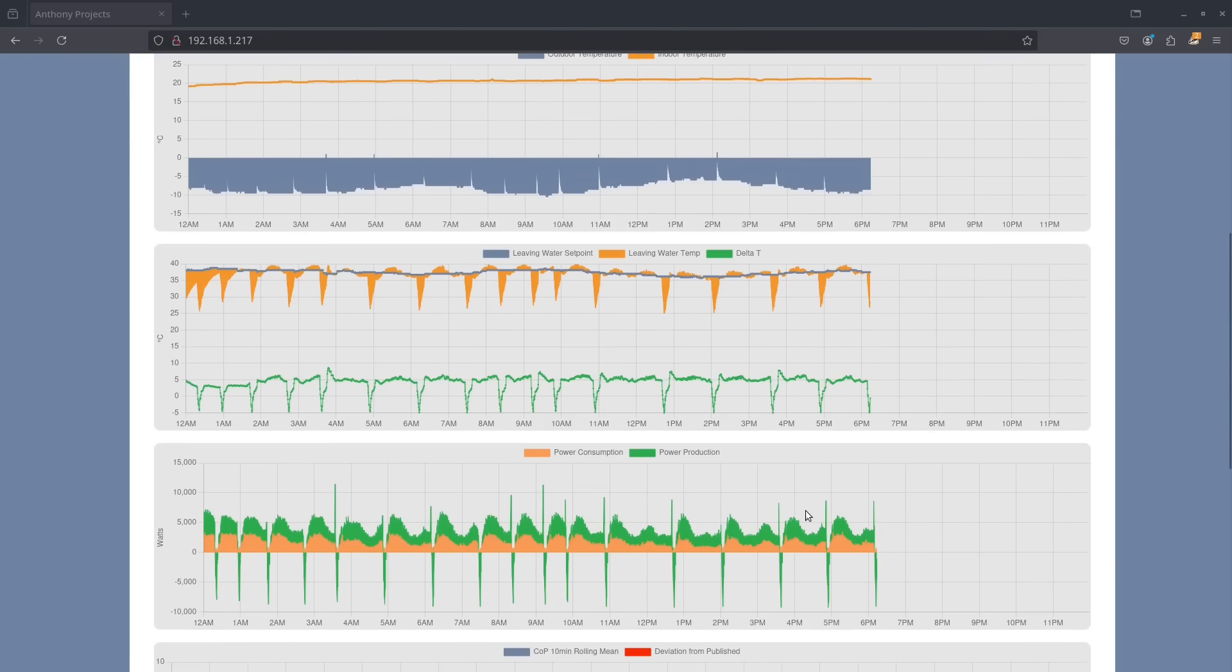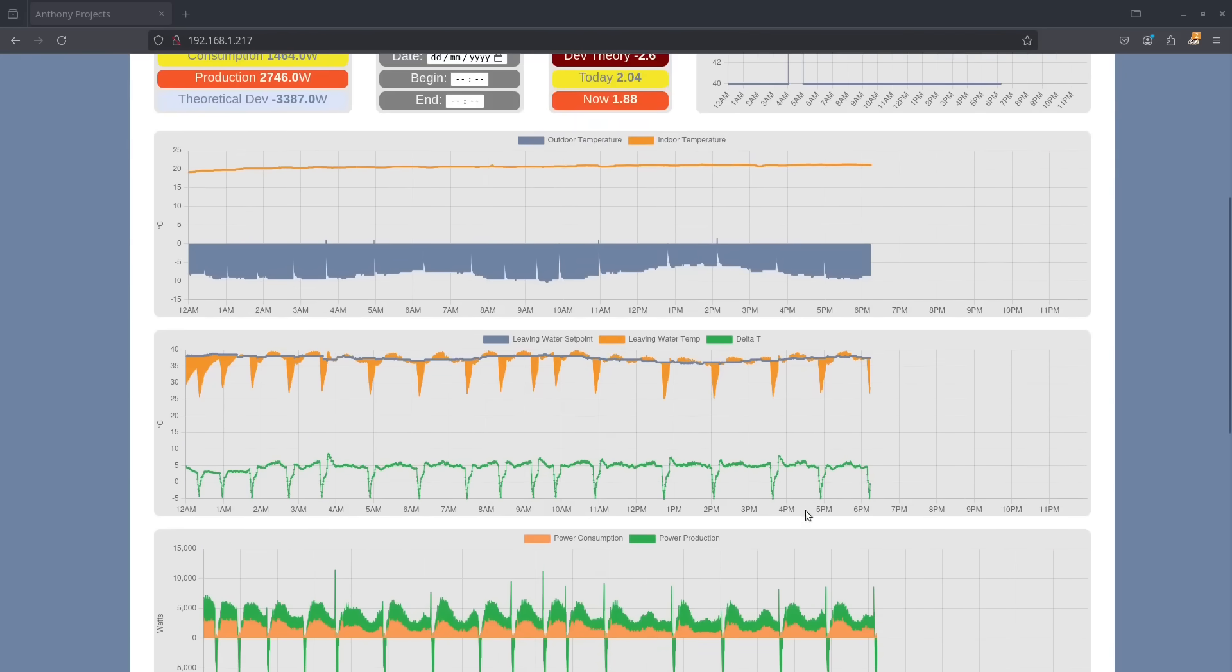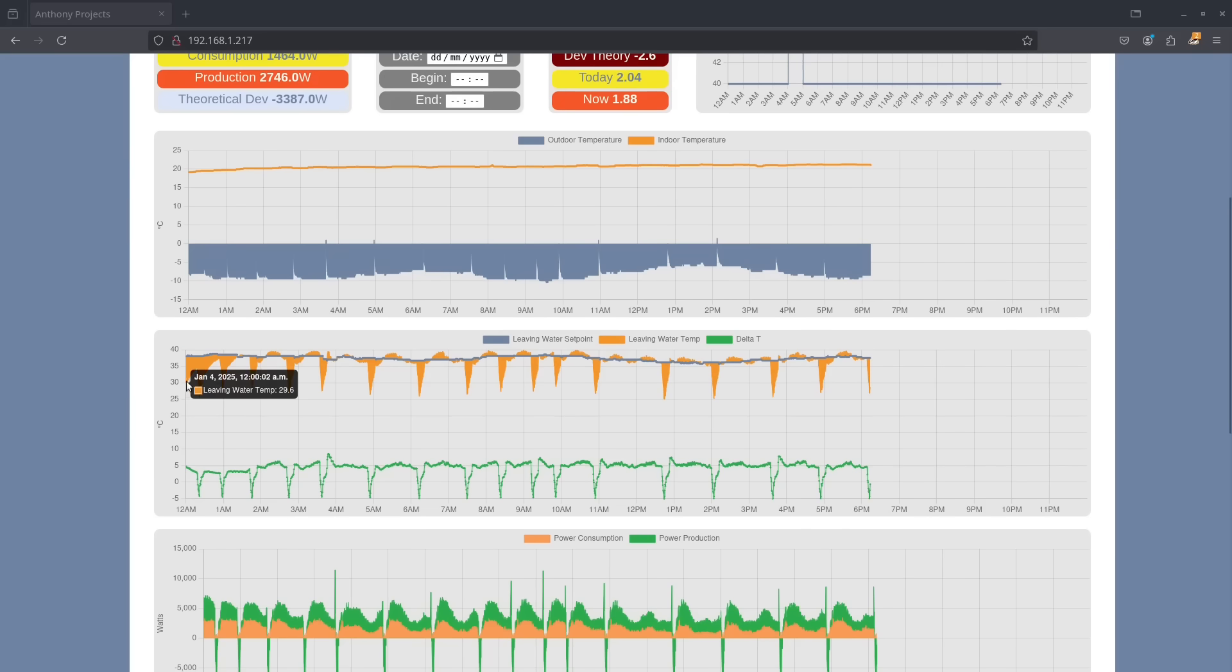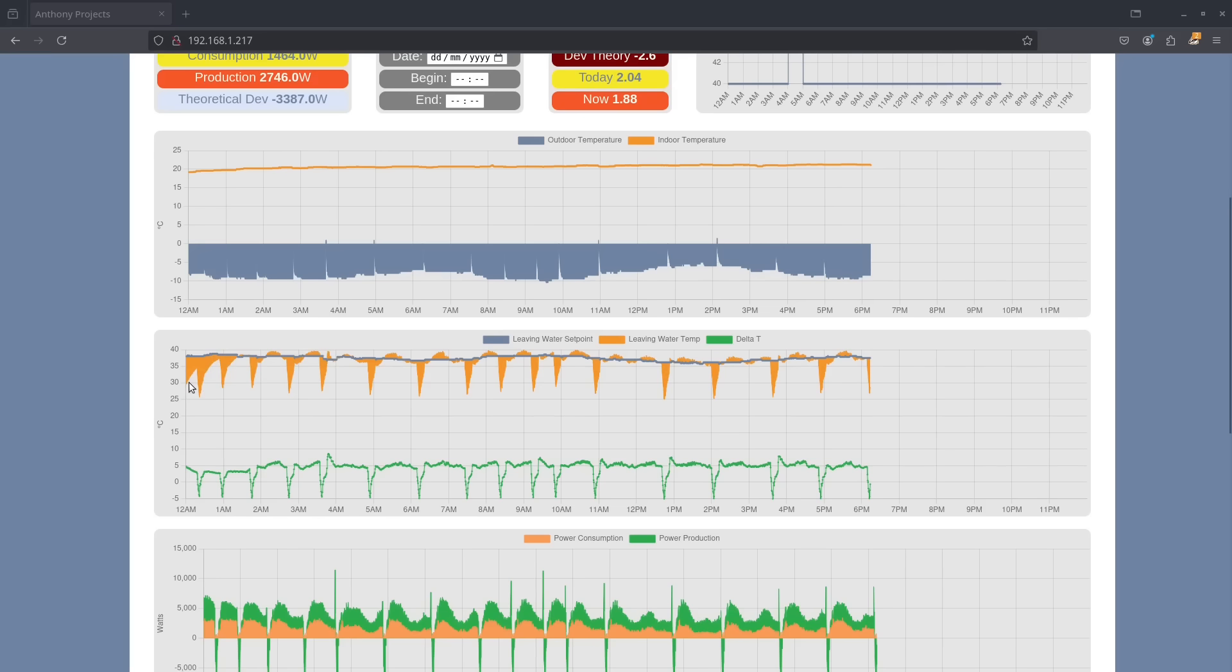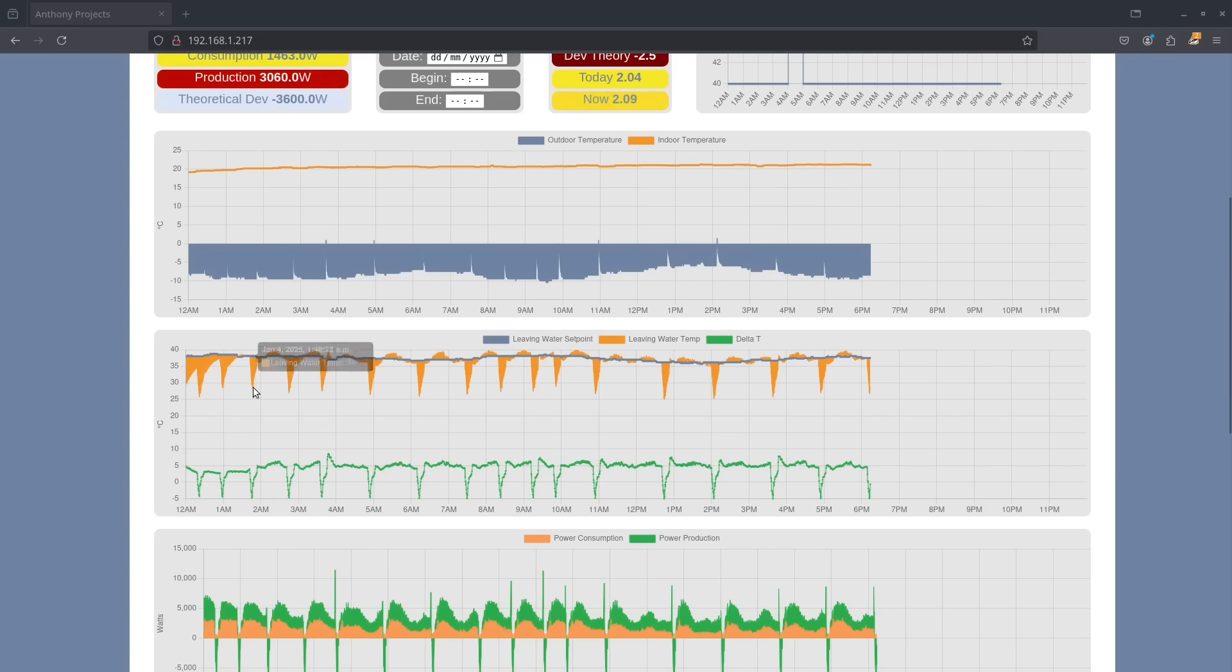Now this is interesting, you can see there's a lot of energy which is needed to bring the leaving water temperature up to the set point. If your radiators are at room temperature there's a lot of energy that needs to be put into the system and it can take about an hour to get the temperature up to set point level. But once it's at set point level it only dips down when the heat pump goes into defrost cycle.